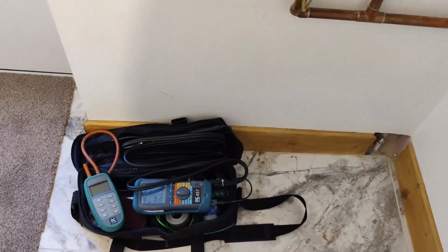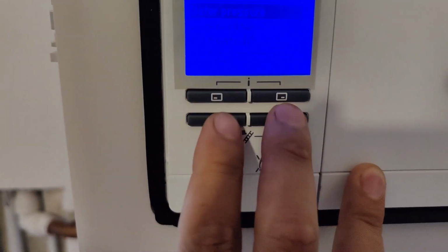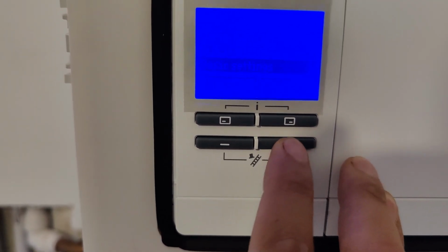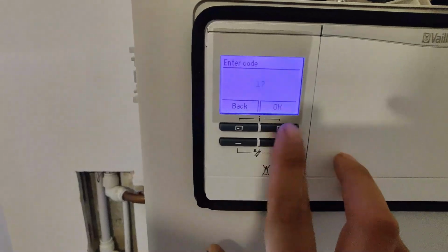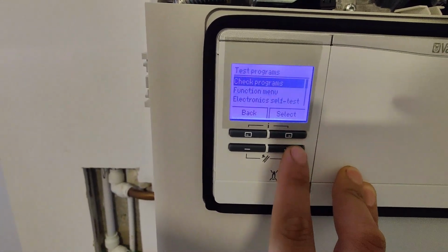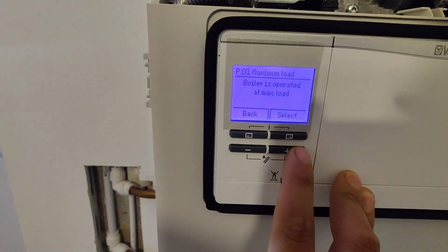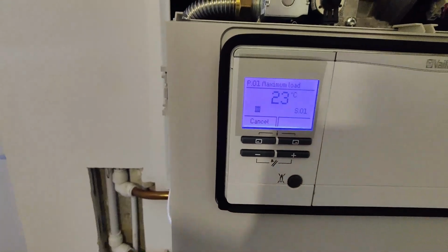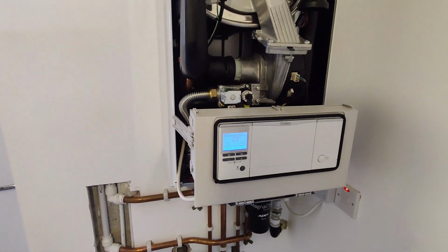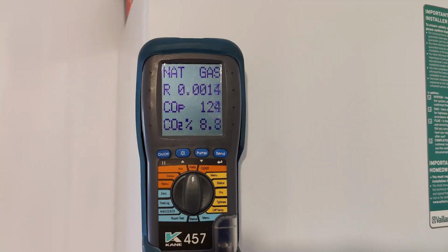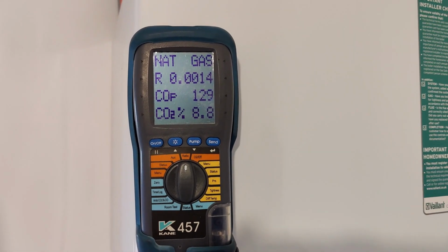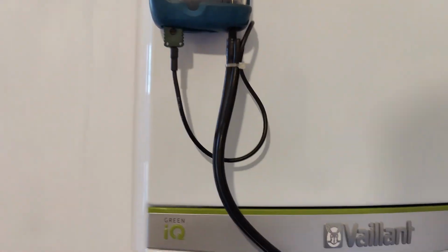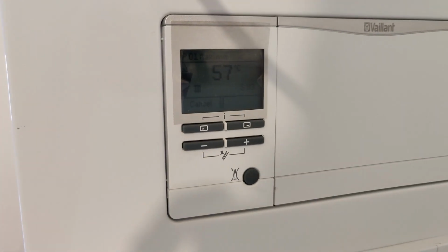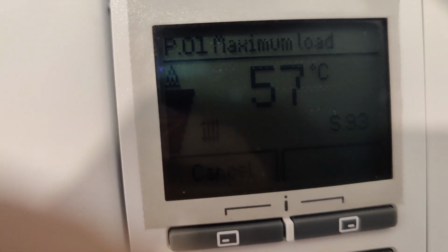Okay, so our flue analyzer is ready. What we're going to do is activate high rate on maximum demand. Okay, test programs, check programs, P01 is maximum load. So that's activated and we will just check the readings. Put the cover back on and get readings. Okay, so the boiler's set to maximum load, still ramping up. P01 maximum load activated.